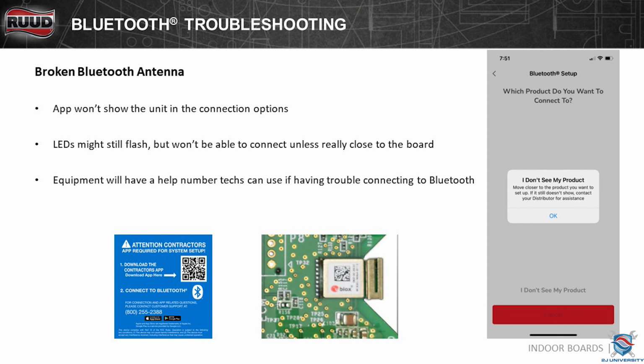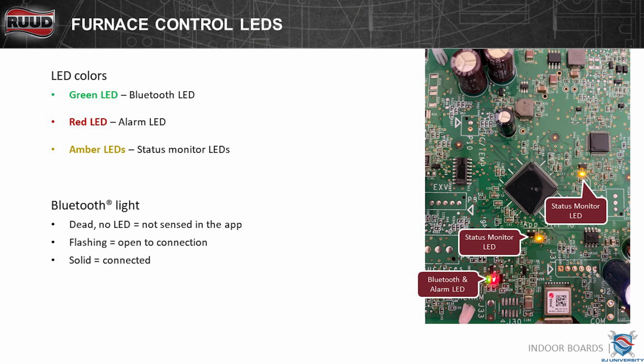Bluetooth connectivity. All the new furnaces and air handlers that have Bluetooth, you'll see this. You can either take a picture of that and pull it up, or you can go to your app store, whether you have Android or iPhone, and you can pull it up through there as well. The boards do have some LEDs on them, and it will give you some status information, but still the easiest way to find that data is in the Contractor app. So always try to go to your Contractor app, connect via Bluetooth, and you can look and see exactly what your status is through there. It'll give you CFM ratings, things like that, if the unit's running.